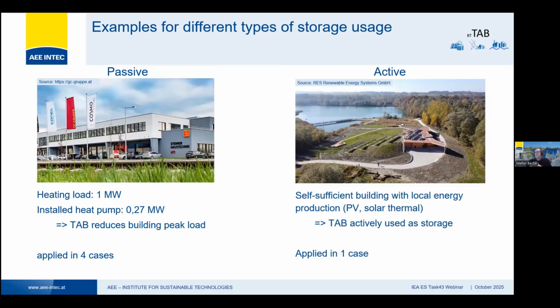On the left side you see a building, quite a huge building with an office part and a large storage hall. The total heating load of this building is 1 megawatt, and the whole building is supplied with a heat pump with a maximal output of 270 kilowatt, well below the heating load. This only works because the TABs reduce the building's peak load, and the heat pump runs 24/7 at maximum power, which is usually the optimal point of operation. This is the passive use.